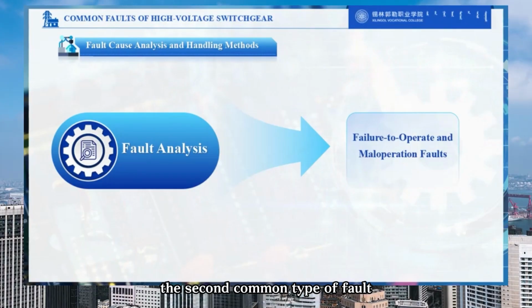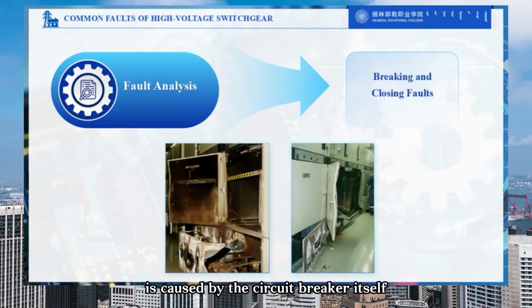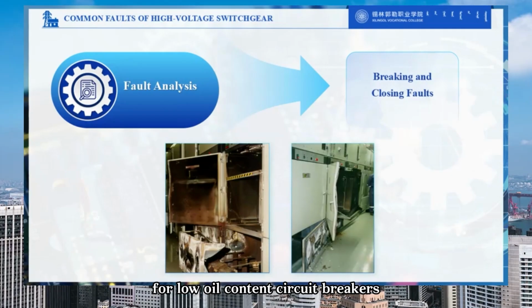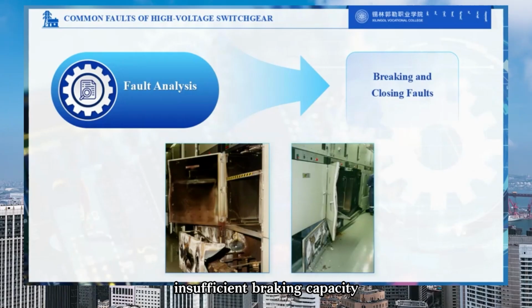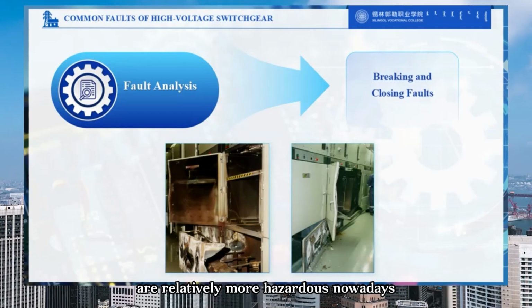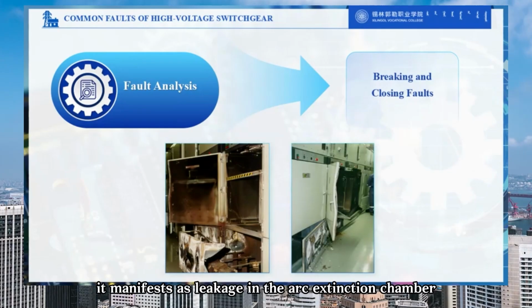The second common type of fault is breaking and closing failure. This type of fault is caused by the circuit breaker itself. For low oil content circuit breakers, it mainly manifests as oil spraying, short circuits, arc extinguishing chamber burrs, insufficient breaking capacity, explosion during closing, etc. Oil circuit breakers are relatively more hazardous nowadays. Most power plants and substations use vacuum circuit breakers more frequently. For vacuum circuit breakers, it manifests as leakage in the arc extinction chamber and bellows, reduced vacuum level, restrike, ceramic tube rupture, etc.